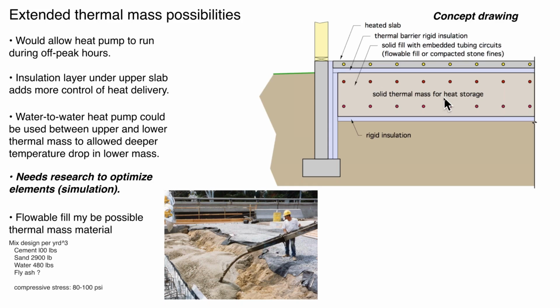I can't tell you, is that optimal? Do we need 3? Do we need 1? That would be where computer simulation comes in to evaluate this. But the concept is we could run the heat pump perhaps during off-peak hours, add heat to this thermal mass, and then when we need that heat, we could bring it to the upper slab.